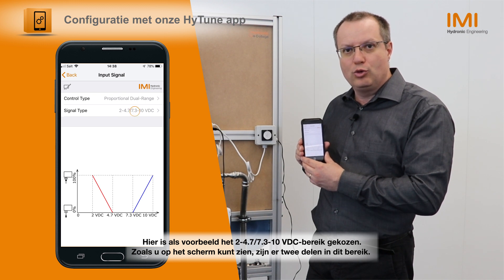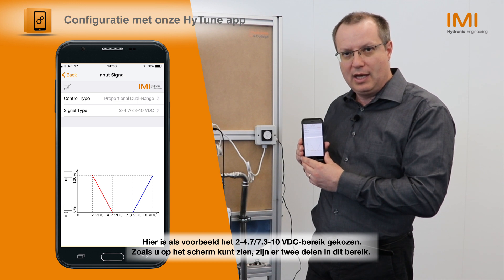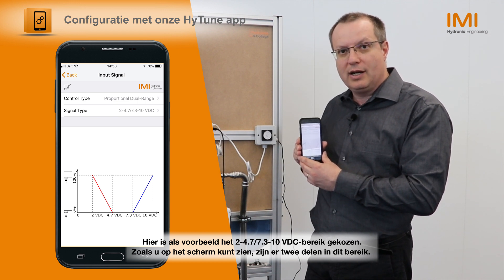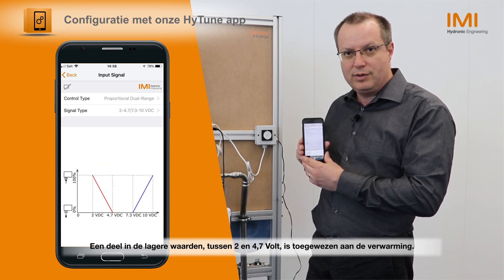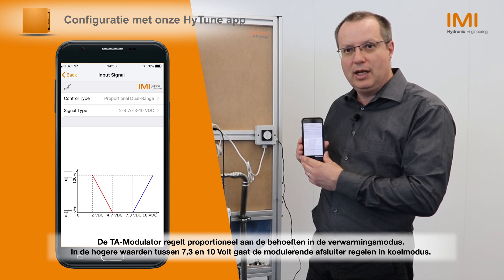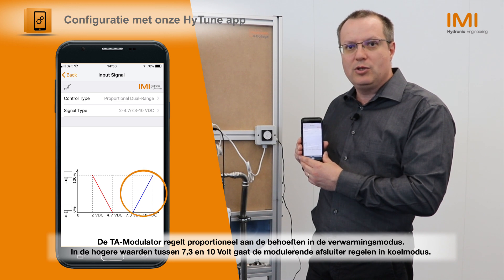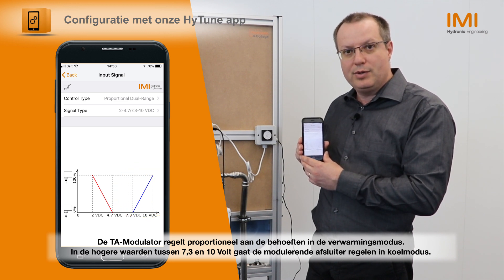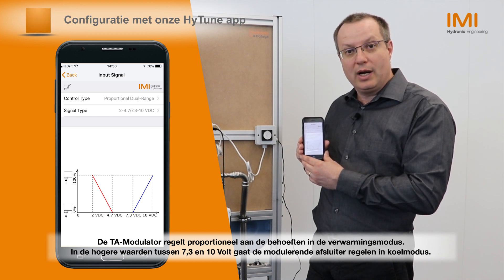Here, as an example, the 2–4.7 / 7.3–10V range has been selected. As you can see on the screen, there are two parts in this range. A part in the lower values between 2 and 4.7V that is assigned to heating and allows the modulator valve to be positioned proportionally to the needs in heating mode. Another part in the higher voltages between 7.3 and 10V that allows similarly to control the modulating valve when we are in cooling mode.